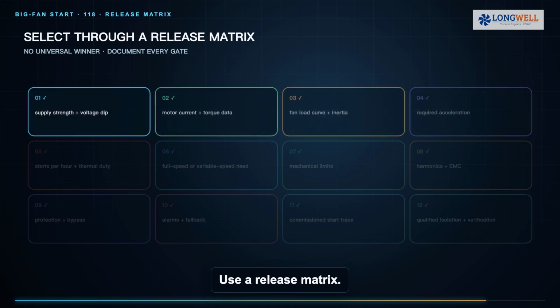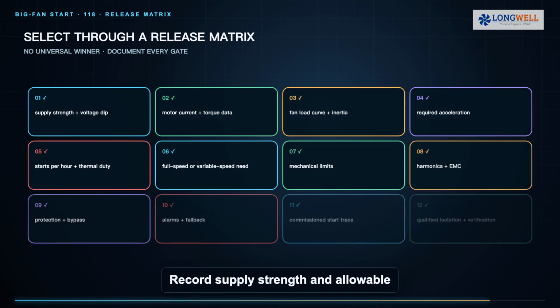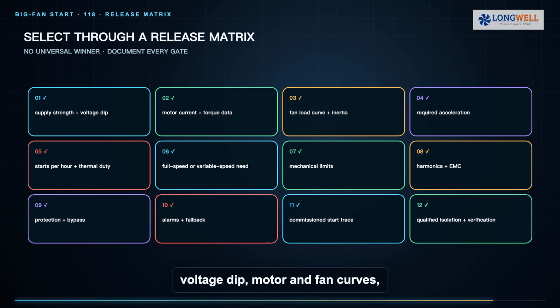Use a release matrix. Record supply strength and allowable voltage dip, motor and fan curves, combined inertia, required acceleration, starts per hour, full speed or variable speed duty, mechanical limits, harmonic and EMC constraints, protection, bypass, alarms, and fallback state. Then select DOL, soft starter, or VFD through an engineered study. Qualified personnel must de-energize, isolate, lock and tag, discharge stored energy, and verify absence of voltage before work.